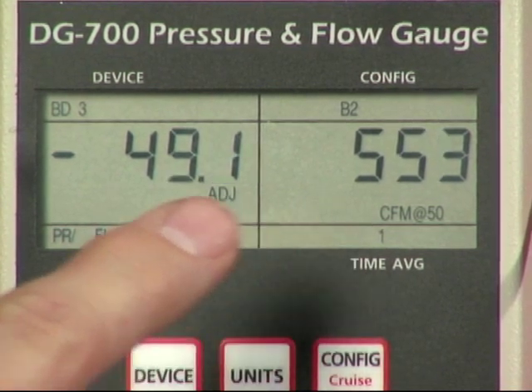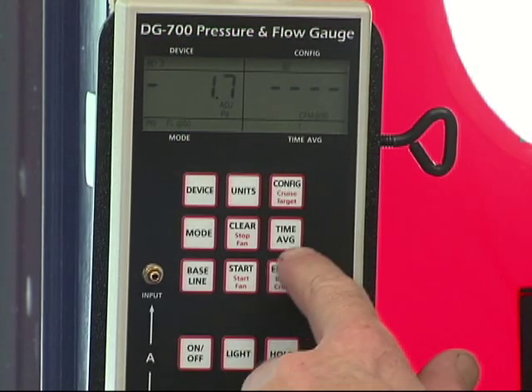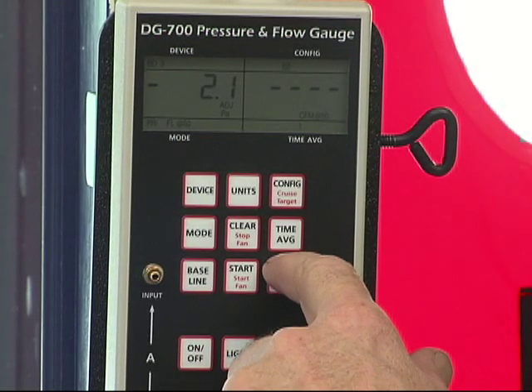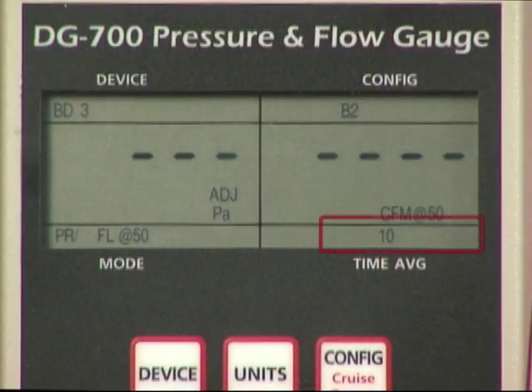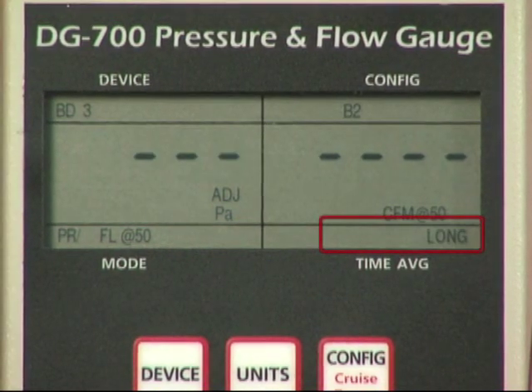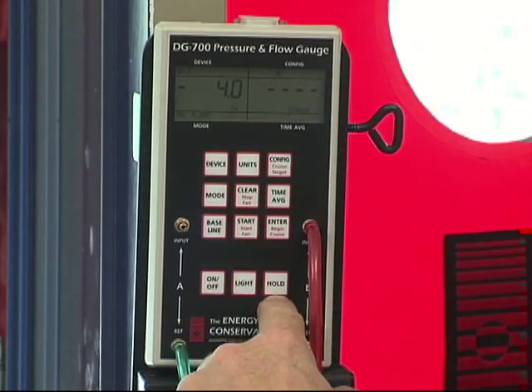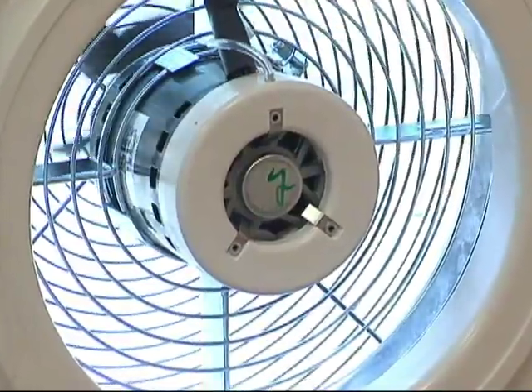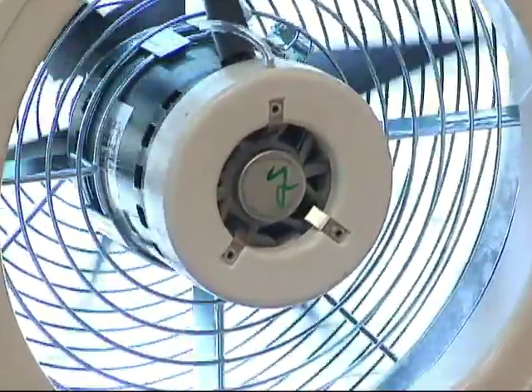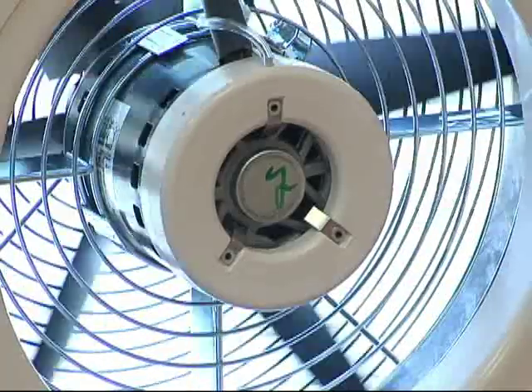If the leakage estimate is fluctuating more than desired, try changing the time averaging setting on the gauge by pressing the time average button and choosing the 5-second, 10-second, or long-term averaging period. Once you're satisfied with the reading, press the HOLD key on the gauge to temporarily freeze the display, record the CFM50 test reading, turn off the fan, then press the HOLD key again to unfreeze the gauge display.